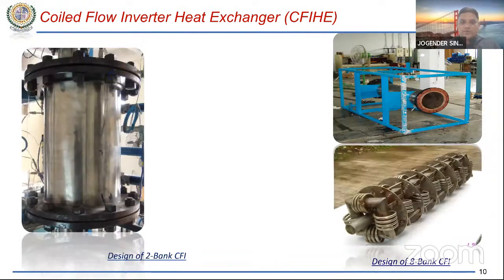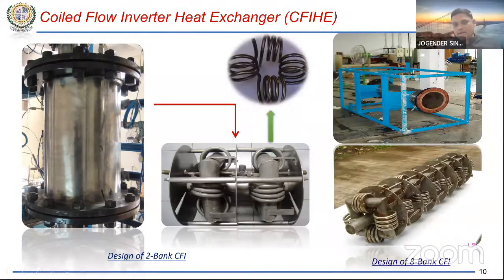Let me give you an idea of how big this 8-bank heat exchanger looks, and how big the 2-bank heat exchanger will be. If you see the right-hand side picture here, this is 8-bank. This is what we call a 1-bank. So 1, 2, 3, 4, 5, 6, 7, and 8. Till the end, we have 8 banks here. It looks like a huge device. After that, we reduce it to, let us say, 2 banks. This is the shell of the 2-bank, and this is 1-bank, of course without the baffles here. And this will be the 2-bank device. You can see that it takes almost 1/4 of the footprint. It is very much less in footprint, 1/4 times less. And we just wanted to test whether it gives the same results or not.